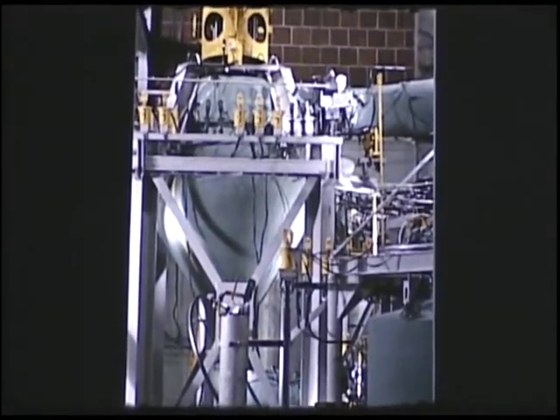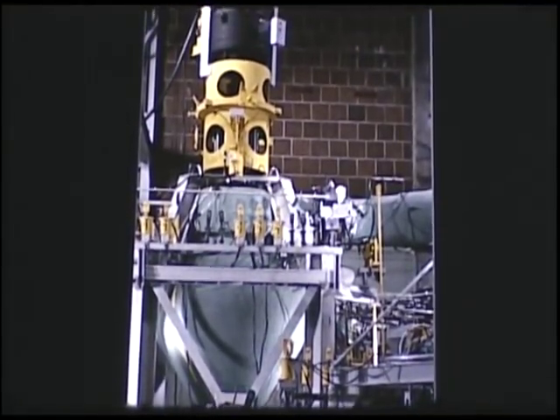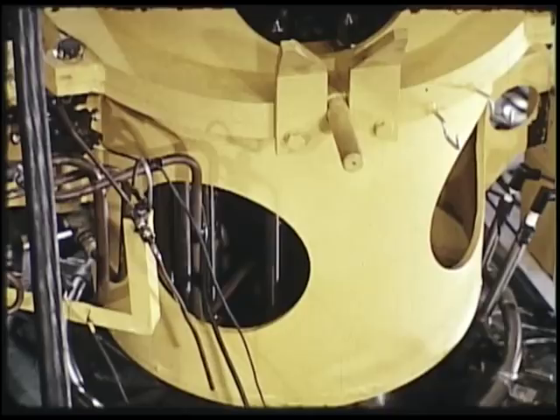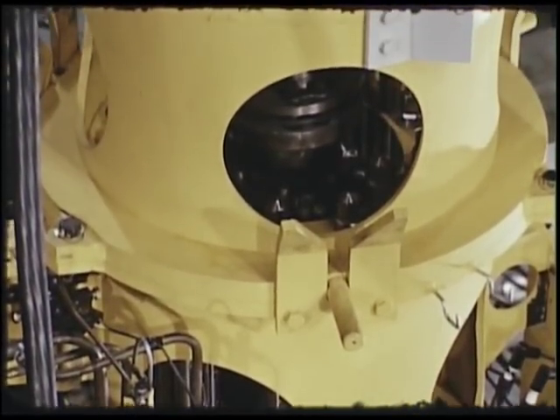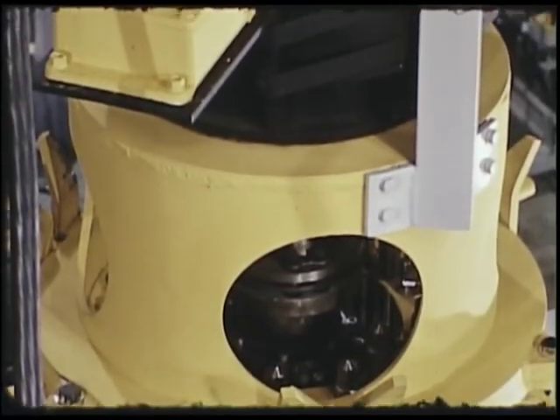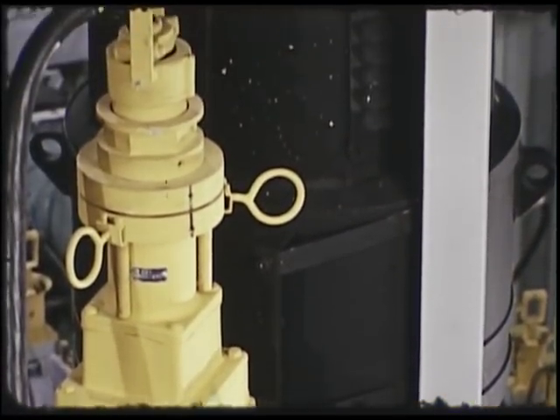Components include a reactor core vessel which supports a centrifugal sump pump and a 30-horsepower DC motor. The pump impeller circulates 460 gallons of molten salt per minute at 28 feet of head. The motor operates at 1,300 revolutions per minute.